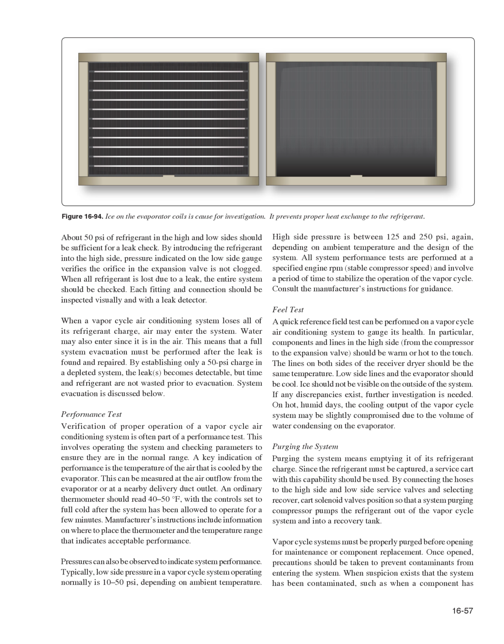Feel test. A quick reference field test can be performed on a vapor cycle air conditioning system to gauge its health. In particular, components and lines in the high side, from the compressor to the expansion valve, should be warm or hot to the touch. The lines on both sides of the receiver dryer should be the same temperature. Low side lines and the evaporator should be cool. Ice should not be visible on the outside of the system. If any discrepancies exist, further investigation is needed. On hot, humid days, the cooling output of the vapor cycle system may be slightly compromised due to the volume of water condensing on the evaporator.